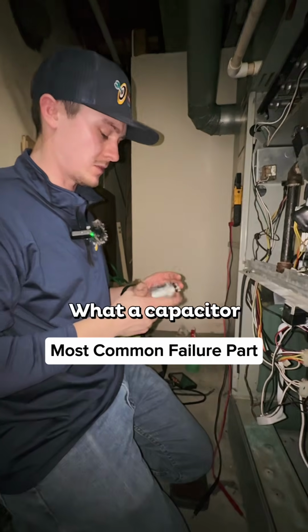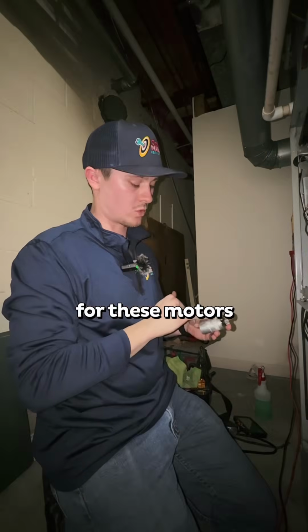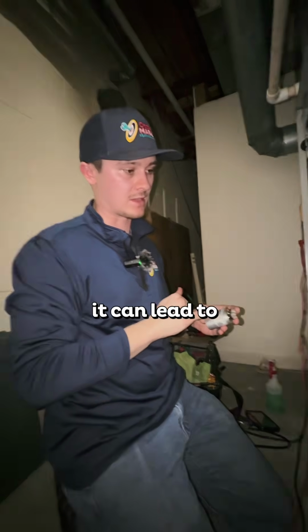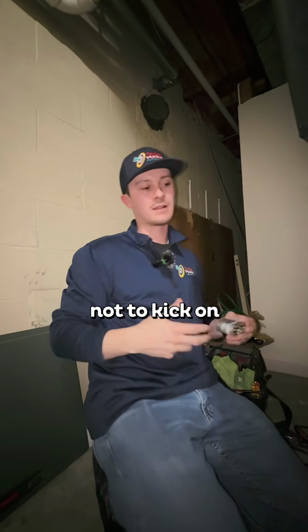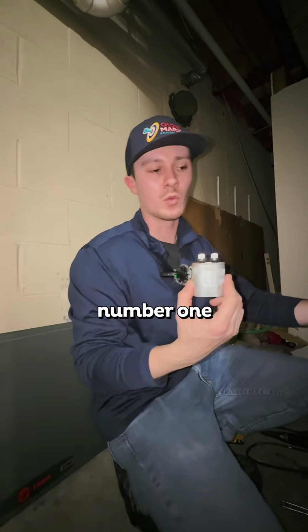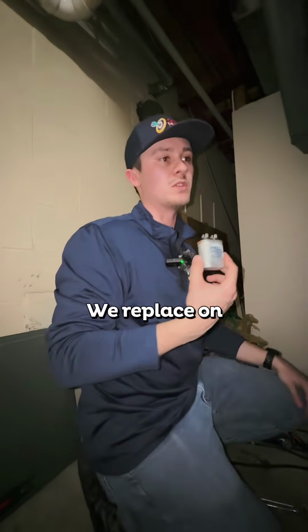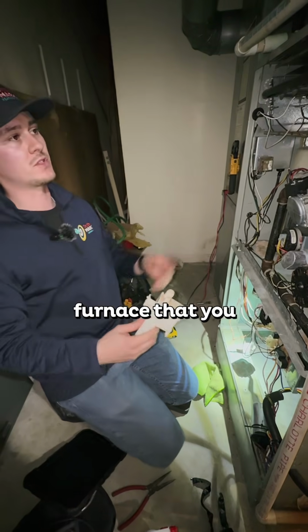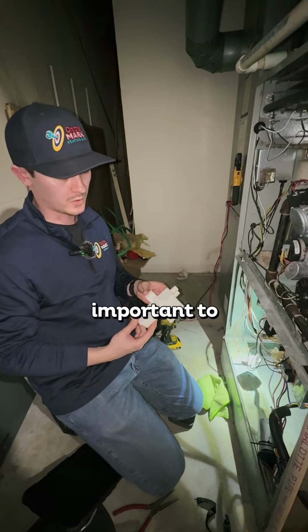A capacitor is one of the most common replacement parts on these systems. What a capacitor is, is kind of like a battery for these motors. Once it gets out of the manufacturer's tolerance, it can lead to causing a motor not to kick on, not to start up. So this is hands down probably the number one replacement wear and tear part we replace on these systems. One of the things on a high efficiency furnace that you have is a condensate trap. It's super important to clean this.